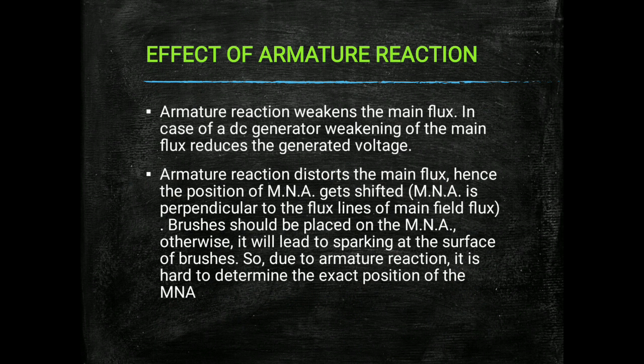Due to armature reaction it is hard to determine the exact position of the MNA, because if the armature current is increased then the armature flux is also increased. If the armature flux increases, it opposes the main field flux more, so the angle between GNA and MNA also increases, meaning more armature reaction. We cannot accurately fix the position of the brush because the MNA axis is not fixed. These are the harmful effects of armature reaction.